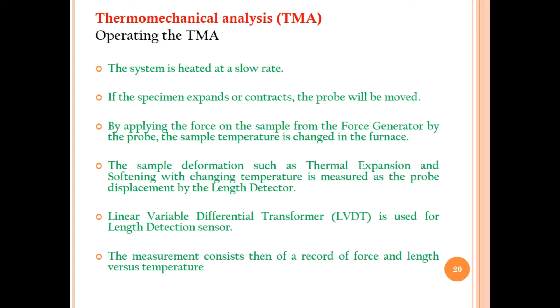The sample deformation, such as thermal expansion and softening with changing temperature, is measured as the probe is displaced, by the length detector LVDT. Linear variable differential transformer, LVDT, is used as the length detection sensor. The measurement consists of a record of force and length versus temperature. So, why is this called TMA? Thermomechanical means its length contraction or expansion as a function of temperature. So, recording the force and the length versus temperature is the basic principle of TMA.